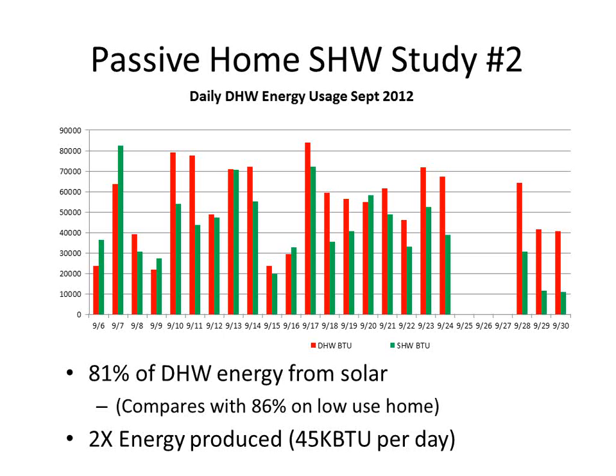Those last couple of days in September, the 25th through 27th, were very cloudy and rainy. If we had that data, you'd see the red bars pretty high with almost no green at all. We were running in the low 90s until then, and that last week we had to run the electric hot water heater substantially. But even in this high load home, using 3 times as much hot water, 81% of the domestic hot water energy came from the solar system.